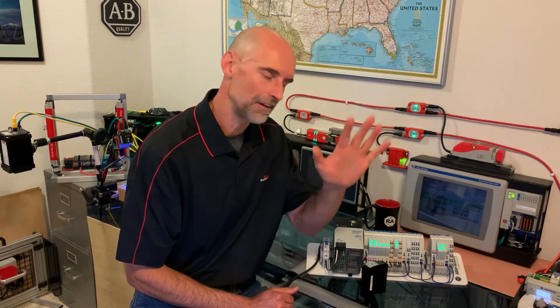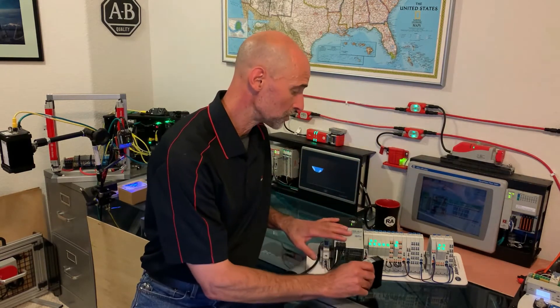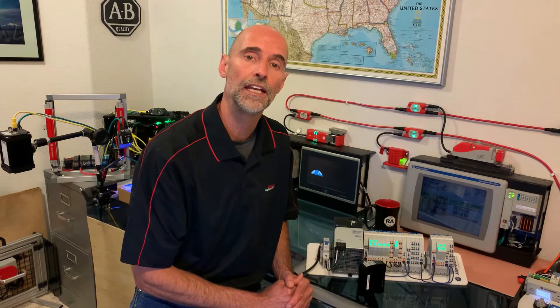Hi, it's Steve Leichen with Rockwell Automation, and today we will take five to discuss best practices around your low voltage power distribution. With many controlled devices moving from 120 volts AC to 24 volts DC, you're probably noticing an increasing number of those devices which require an SELV or PELV power source, or maybe they require or specify for use in an NEC Class 2 circuit only.